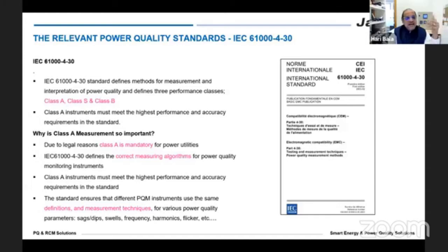The standard clearly defines two categories, Class A and Class S. Class A is more of a specific standard, and Class S is more or less a declaration. People can declare that this is what they are testing against, and then they will get Class S. But with Class A, that is why I said, when two Class A meters are used with the same configuration at the same point, the readings would be more or less the same value across both.